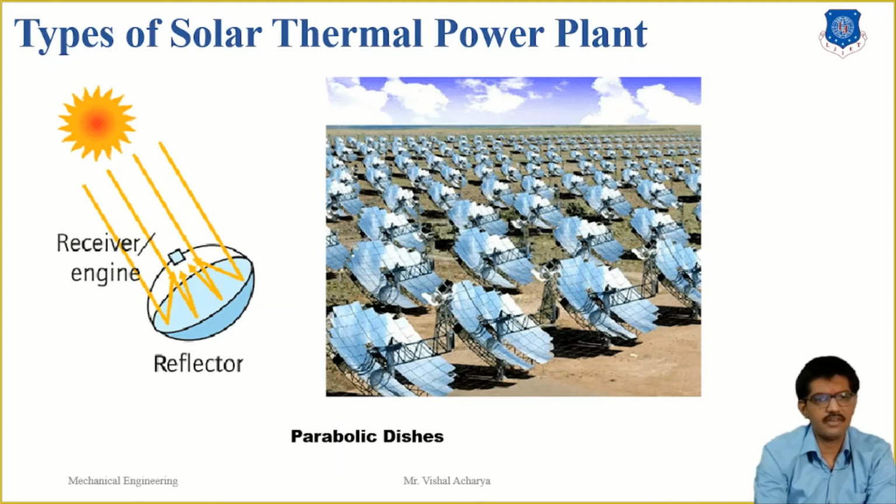Second is the power conversion unit. The power conversion unit includes the thermal receiver and the engine generator. The thermal receiver is the interface between the dish and the engine generator. It absorbs the concentrated beam of solar energy, converts the energy to heat and transfers the heat to the engine generator. A thermal receiver can be a bank of tubes with a cooling fluid, usually hydrogen or helium, that typically is the heat transfer medium and also the working fluid for an engine.